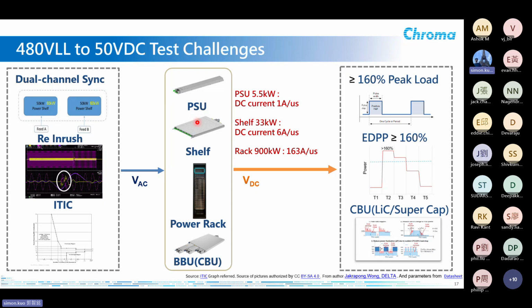Back to the fundamentals. Each power supply is defined clearly in the OCP specification for the ORV3: each power supply of 5.5 kilowatt will need to fulfill a DC current slew rate of 1 amp per microsecond. The shelf is fixed to 6 units maximum, so we multiply by 6. Then we are looking at the power racks, which is the sidecar. The power rack is now reaching 900 kilowatt and it's even scalable. So we are looking at around 900 kilowatt, so it's in total 163 amperes per microsecond.